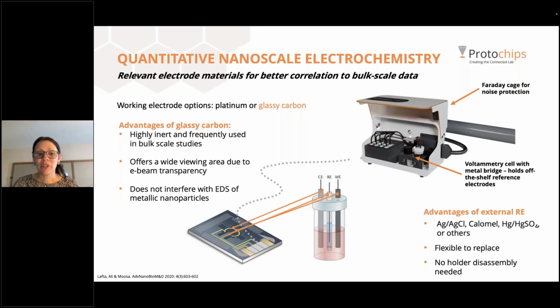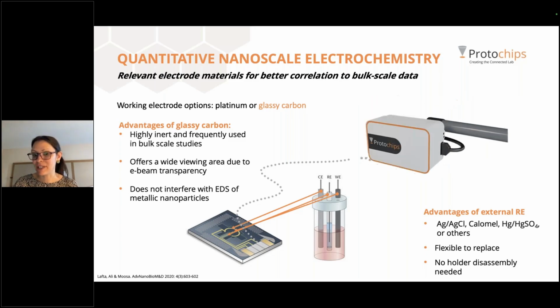To expound upon the electrochemistry just a little bit that's happening during those temperature changes, your working, counter, and reference electrodes are all here, patterned on your chip. You do have the option of using an external standard reference electrode though, something like silver chloride or saturated calomel, which will help compare to bulk experiments even more seamlessly, because that's what you're typically using on a larger or benchtop scale. And again, I mentioned the multiple electrode options for the working electrode, such as glassy carbon or platinum. All of them have been optimized, again, the design and the orientation of them, for EDS measurements during the experiment.